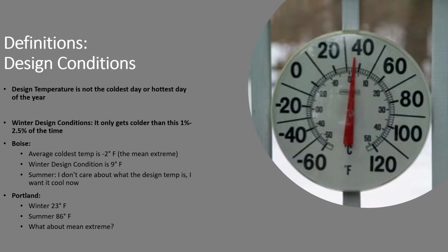Let's get some definitions out of the way. Design temperature is not the coldest day of the year or the hottest day of the year. Usually the coldest day of the year happens at 2 or 3 in the morning. Chances are the house has enough thermal mass that it's already heated up and can ride through those few cold hours. If we sized equipment for the hottest or coldest day of the year, we would probably have 2 systems in every house, and everything would cycle, with lots of comfort complaints. Winter design condition means it only gets colder than that 1 or 2.5% of the time, depending on what number you use. In Boise, the average coldest temperature is -2. This is also called the mean extreme. However, the winter design condition is 9.